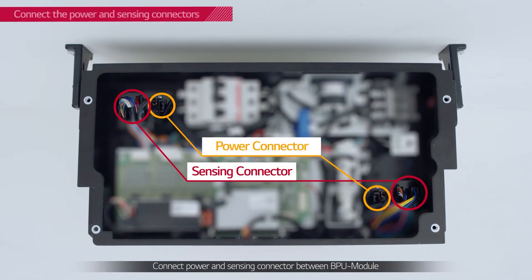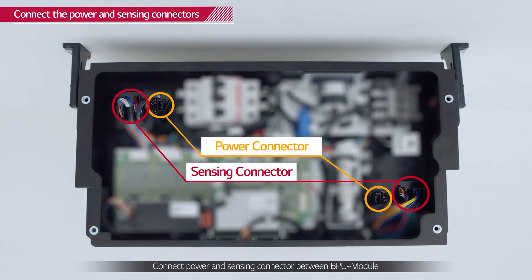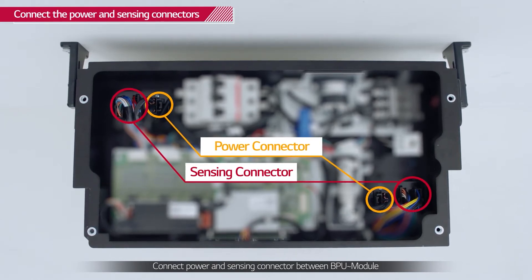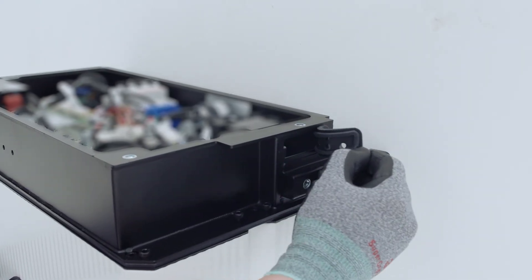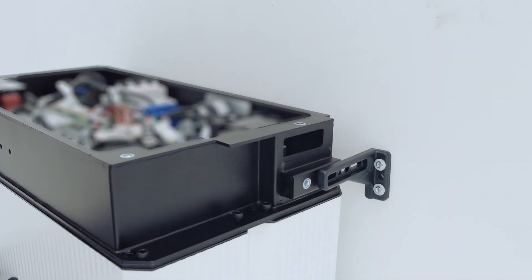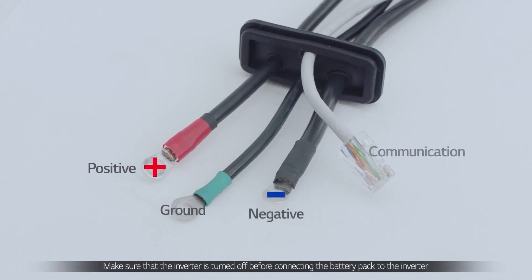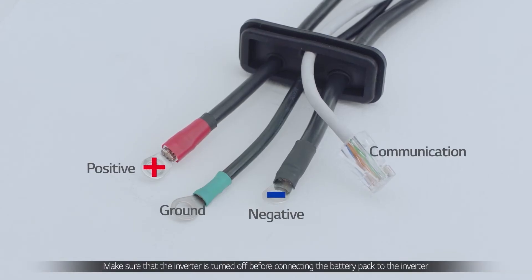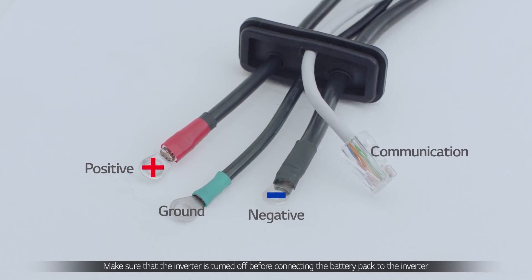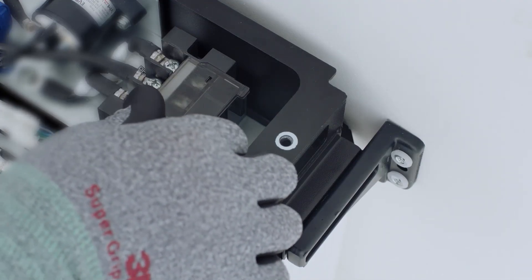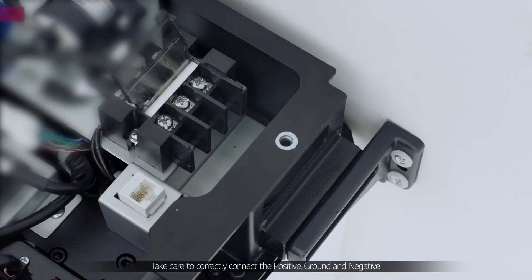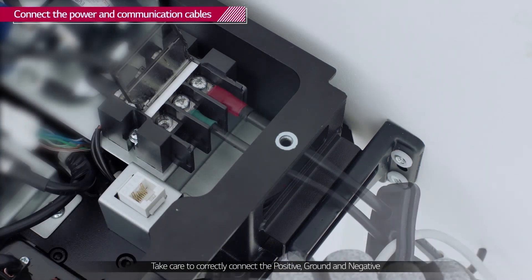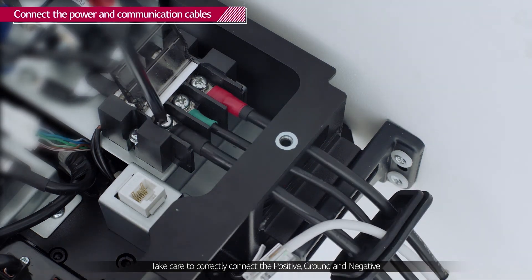Connect the BPU power and sensing connectors to the battery modules. Next, feed the power cables, ground cable and communication cable through the grommet to the right of the battery modules. Connect the power cables first. Open the terminal cover plate and connect the power cables and ground cable to the BPU respectively with the cross socket screws.